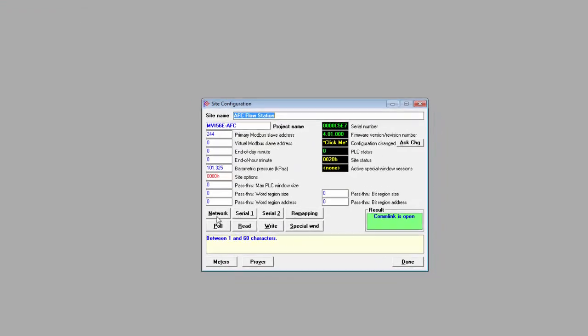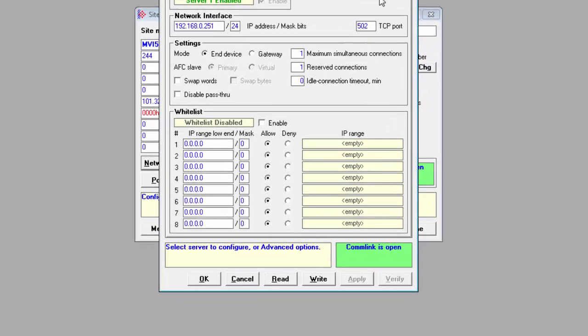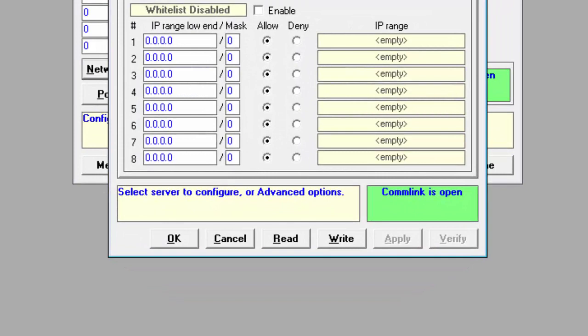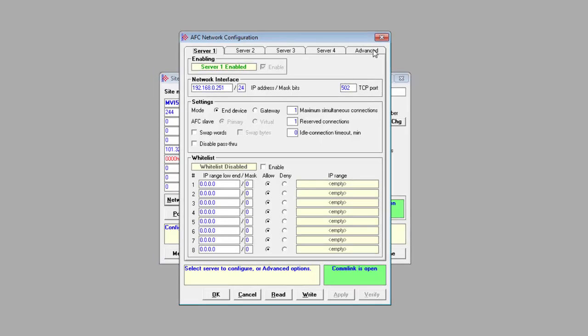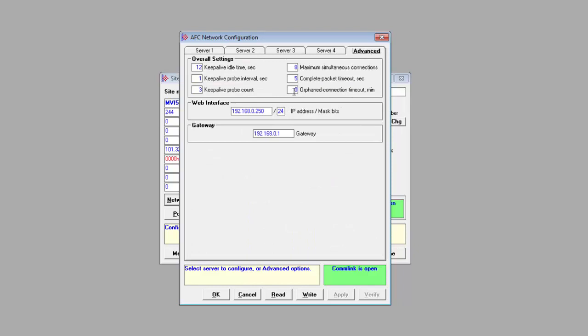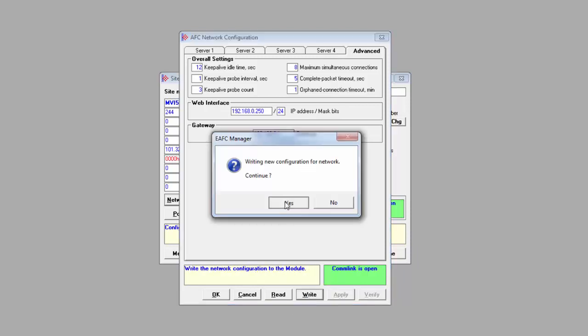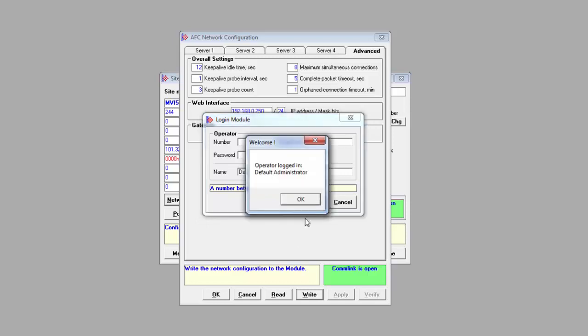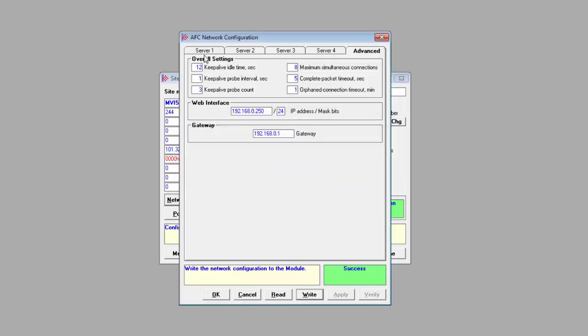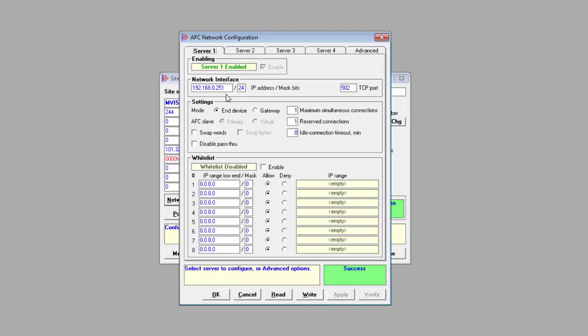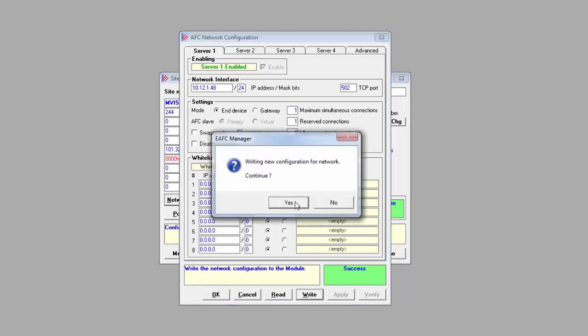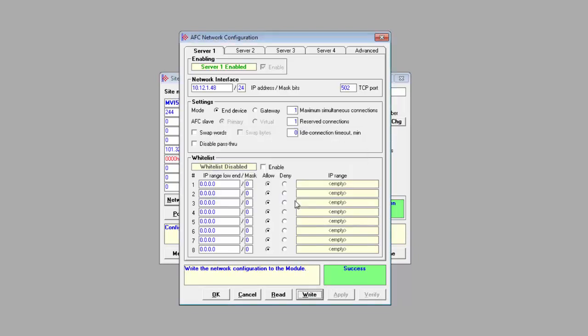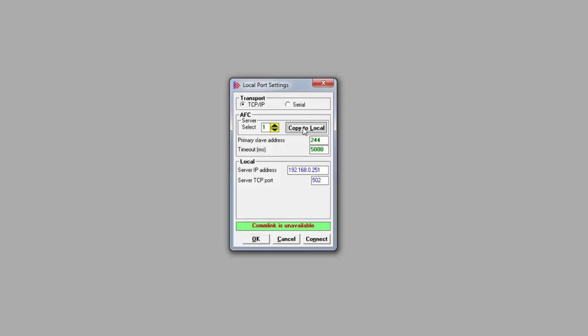We'll set the permanent IP address now. This is also a good opportunity to show that a full project download is only required the first time a project is downloaded to the module. Afterwards, each configuration section has its own read and write buttons. So changes can be made to these sections and then be written to the module without having to download the entire project. So if I go to the network advanced tab and set the orphan connection timeout to 1 minute, I can apply this and then click write to change just this part of the configuration. Then we'll return to server 1 and change the IP to what we'd like to use in our application. And again, click apply and write. This will change the module's network IP address. Note that our connection will be lost after we do this. We'll have to switch to the new IP and its associated subnet in order to reconnect.